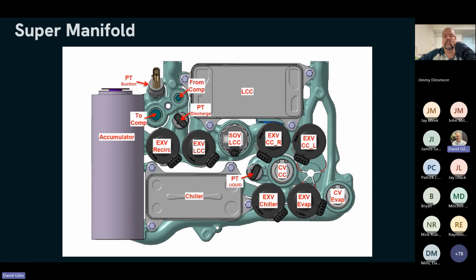These solenoids are actually either on or off, or they can be pulse width modulated. So if they all failed and stuck shut and the compressor is compressing, the pressure would go extremely high. This SOV, basically for the LCC, opens up and relieves the pressure from the system, so it doesn't allow the system to become damaged or cause failure.